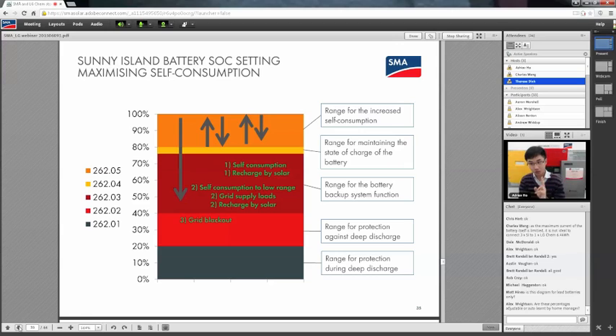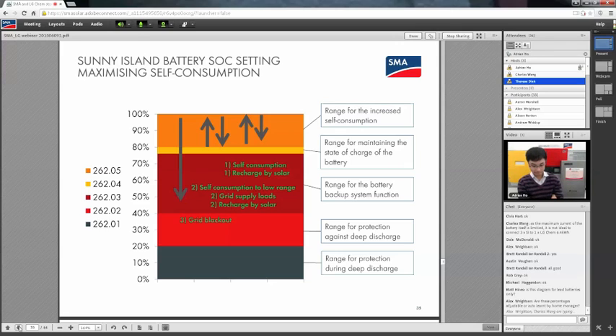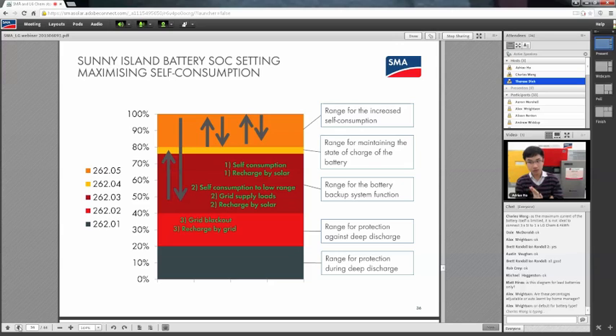At 45%, now the grid restores. What will happen now? Some of you may already know. The system will use the grid energy to charge the battery and also supply the loads, charging into the yellow zone - halfway up into the yellow zone, which in our case is 78%. So from 45%, using full grid power, full peak tariff power, up to 78%, and then it stays there.